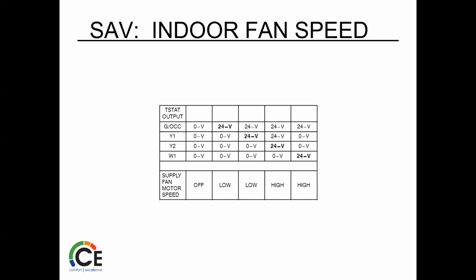Indoor fan speed, again, we're talking about staged air volume. The 7220 does not determine fan speed. It just knows there will be a fan speed. So again, depending on what the inputs are, the system kicks back in and decides what the fan speed is going to be.